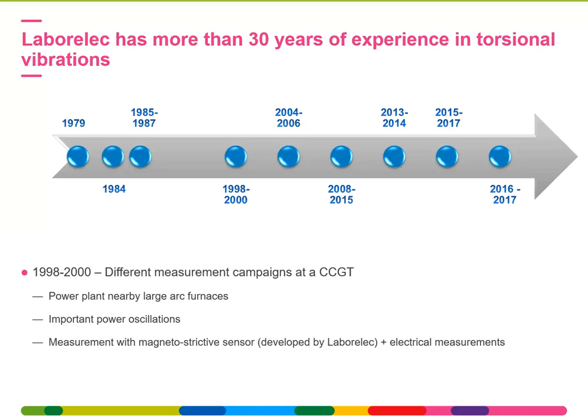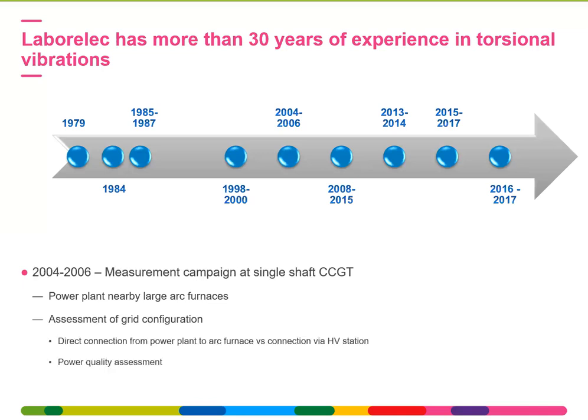Here, for instance, is one at a combined cycle gas turbine in the late 90s, where the power plant was located nearby large arc furnaces known to potentially interact with the power plant. There the power plant experienced important power oscillations, and a measurement campaign with the magnetostrictive sensor developed by Laborelec was done, as well as electrical measurements, to determine the cause of these torsional vibrations and to show the insurer that the large arc furnace is the cause for the torsional vibration amplitudes at the power plant.